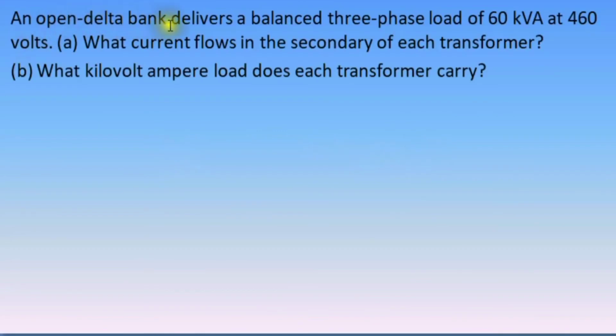Now we have problem number 4. An open delta bank delivers a balanced 3-phase load of 60 kVA at 460 volts. Letter A, what current flows in the secondary of each transformer? And letter B, what kilovolt ampere load does each transformer carry? So that is an open delta bank. Its load is 60 kVA at 460 volts.